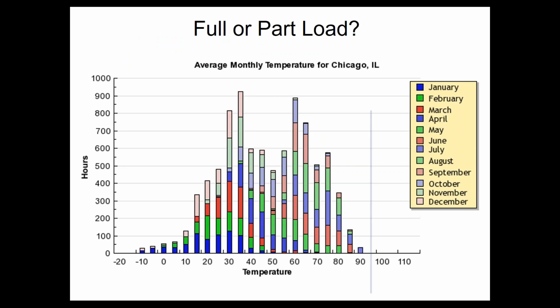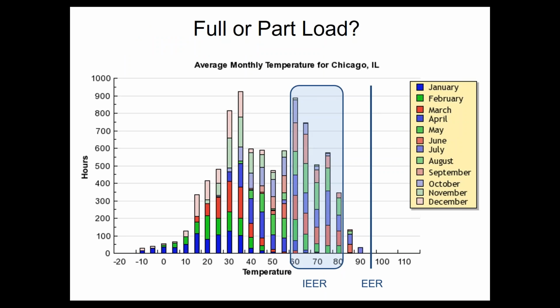You saw this chart before, but it comes into play again over here. Equipment historically, as you know, has had an EER rating, energy efficiency ratio. That is, how efficient is this equipment on a 95-degree day outside with 80, 67 return air conditions? Something that probably doesn't happen in most places of the country. I don't really care how efficient this unit is on a 95-degree day. That day hardly ever happens. How efficient are you on an 85-degree day or 75-degree day?